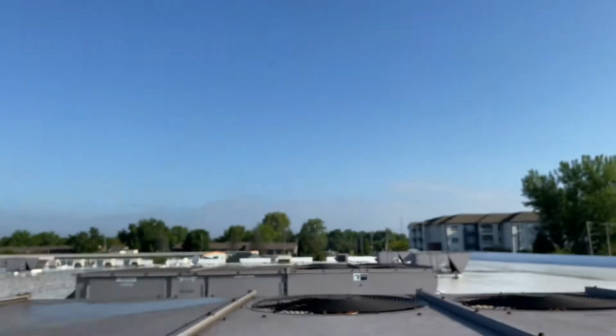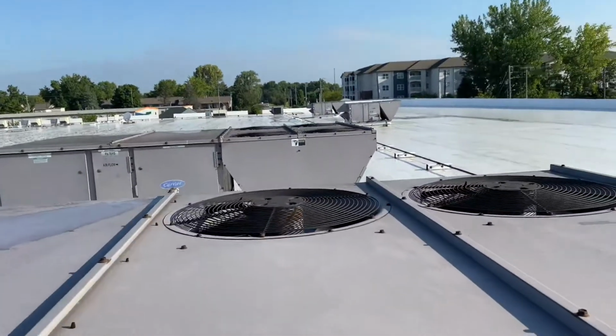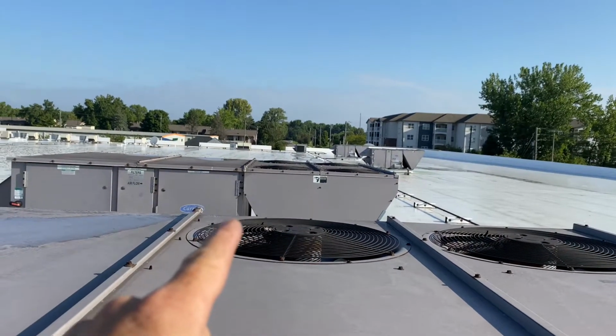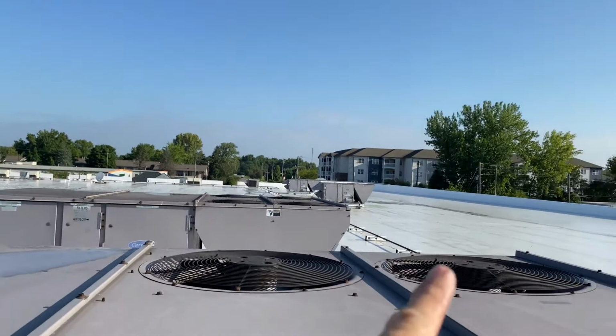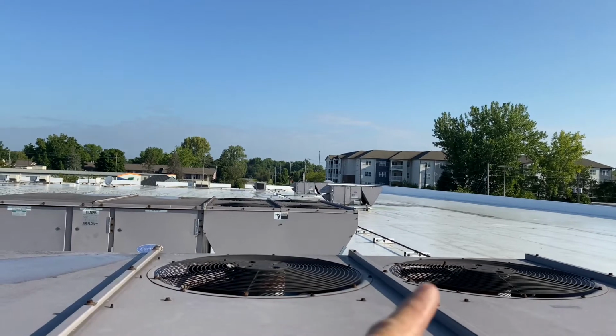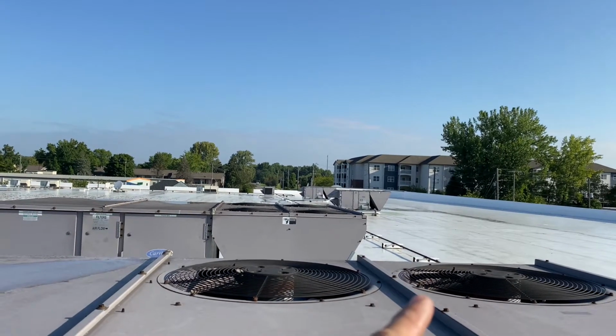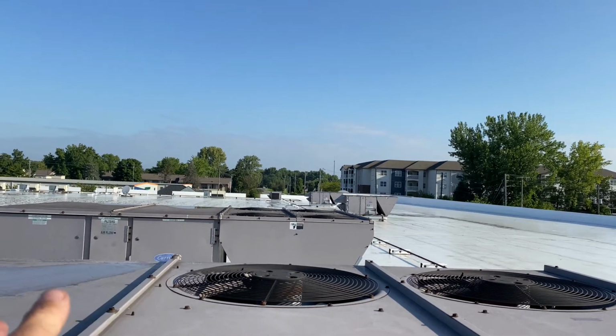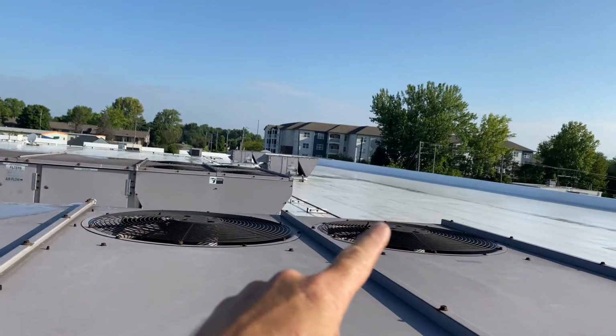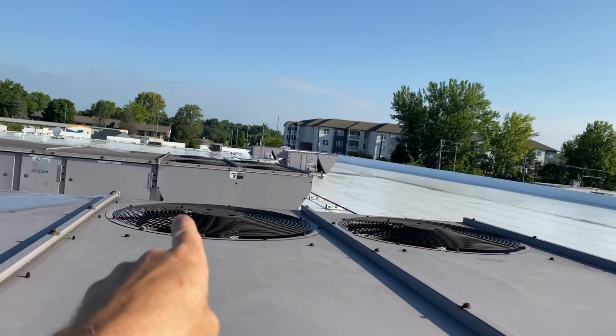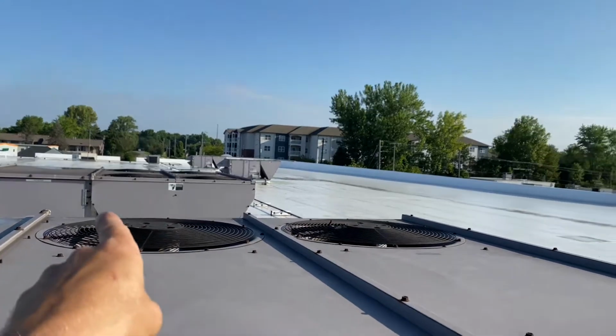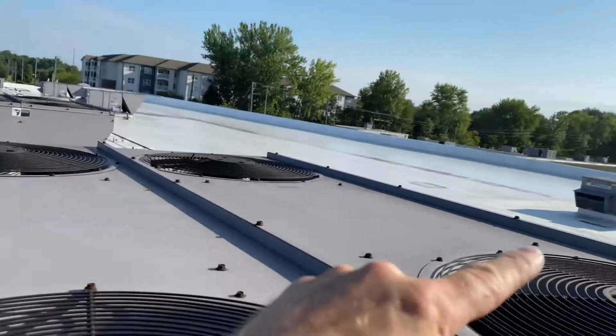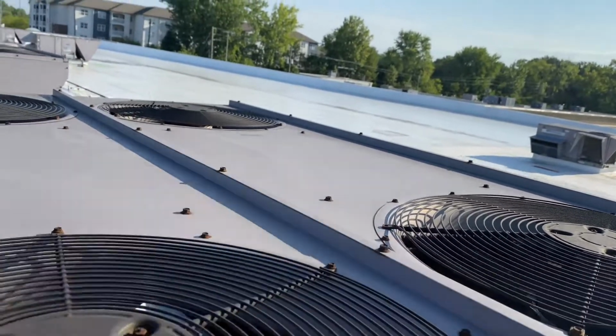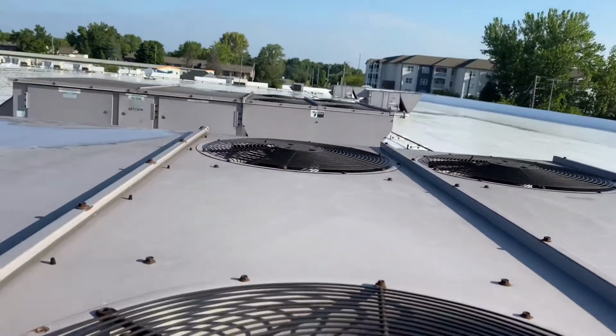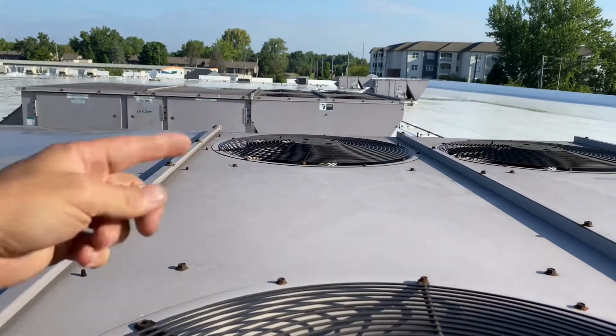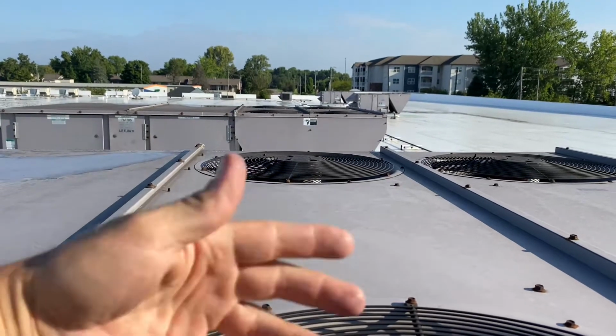I'm gonna pull off the top grill for this fan, unland the motor wire for these 2, and then go back and, well, I guess not these 2, because possibly that one runs. This is one where I saw the spark. Unland this one, which is 3, and then land this one, which is 1. So, and then go through, I'm gonna re-land the wires back on the contactor to make sure everything's good.